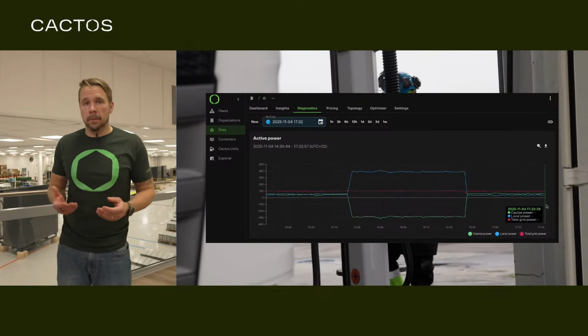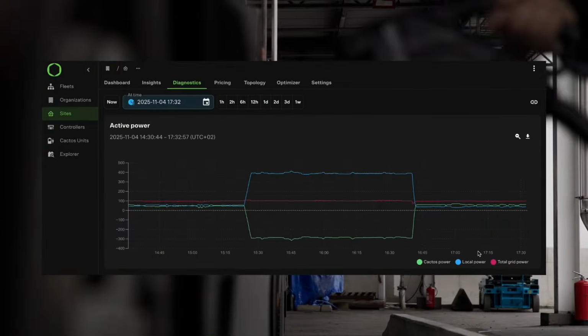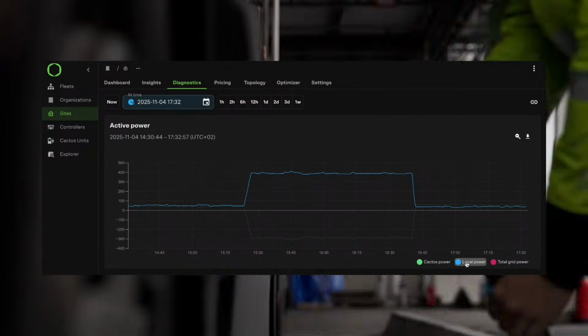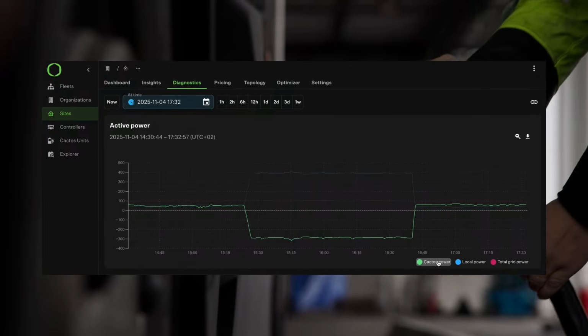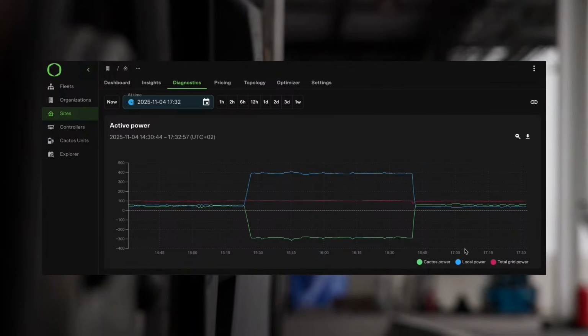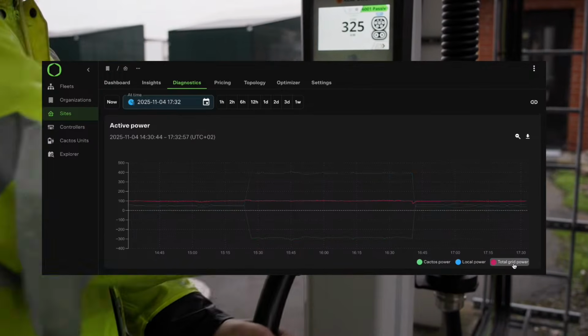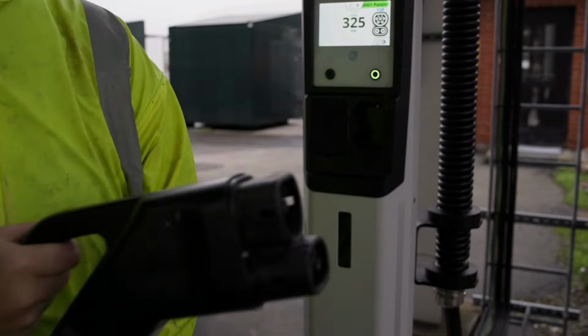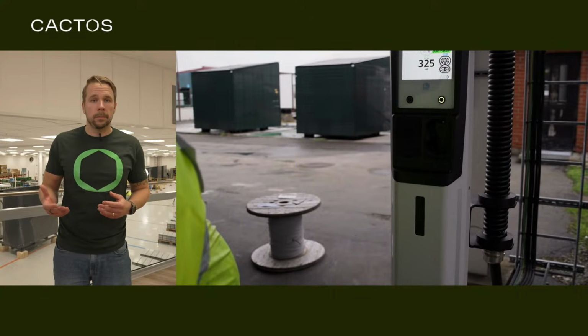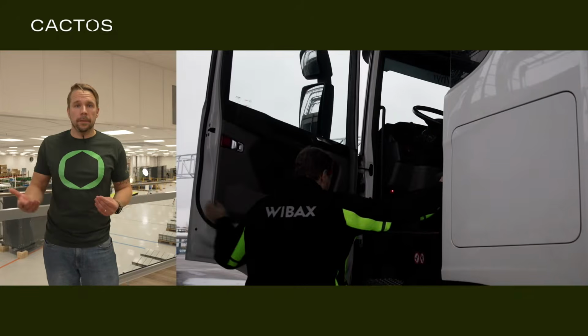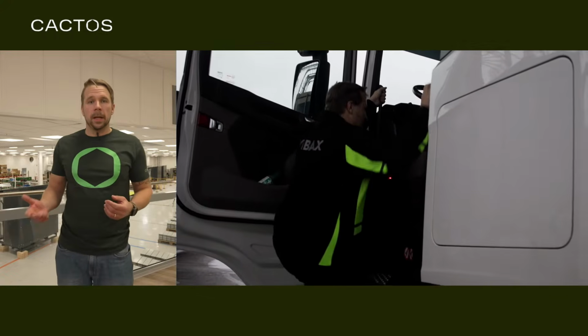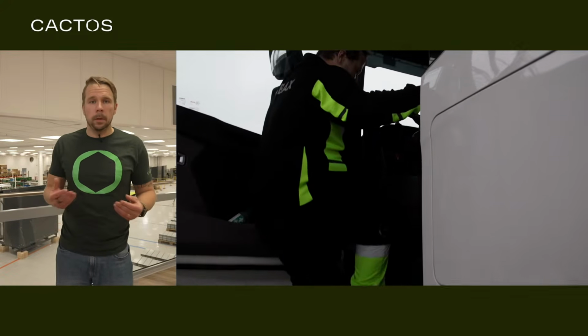In one location, WIBAX is electrifying their fleet of delivery trucks and needs to charge them at their chemical terminal. The issue they face is that the trucks charge at more than 400 kilowatts, but the DSO only gave them a 100 kilowatt connection—so they had a 300 kilowatt problem on their hands.